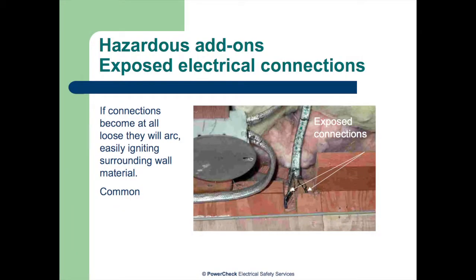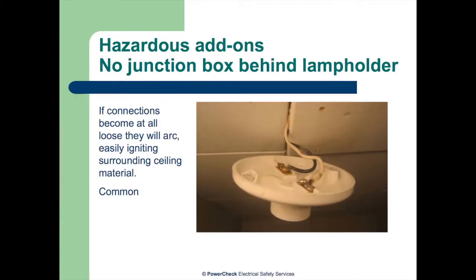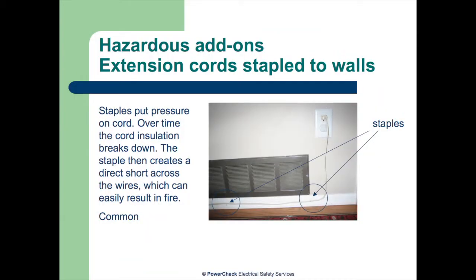What do we got here? Handyman add-ons. No junction box behind lights. Staples. People say, what's wrong with the staple? It makes it look nice. Well, a staple, what's a staple made out of? Metal. It's all fine, but a staple's putting pressure on the insulation. It's putting pressure on the wire. And then one day that insulation gets cracked and there's a little tiny crack in there. And then the staple is now making direct contact between the hot and the neutral. Boom. Fire.